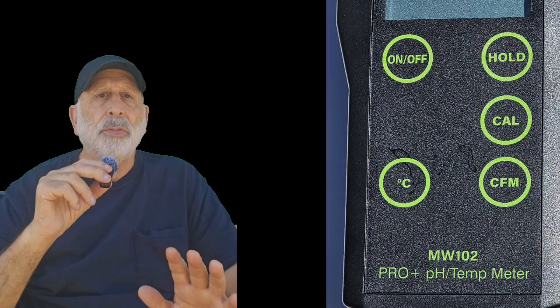Here's an important point about the second solution. When you place the probe in the second solution, like 4.01 or 10.01, you must press Confirm. If you do not press Confirm, the meter will not save that step. So even if you put the probe into 4.01 and wait for it to stabilize, the second point is not stored until Confirm is pressed. Without that final confirmation, you only have a 1-point calibration at 7.01, not a full 2-point calibration.